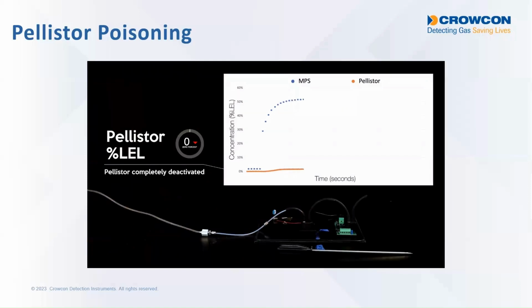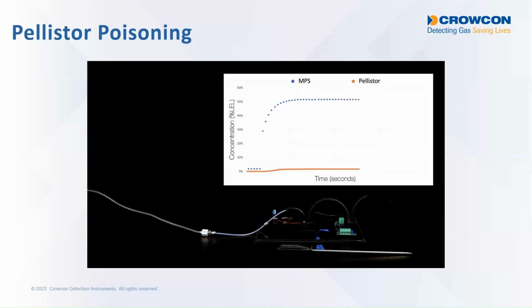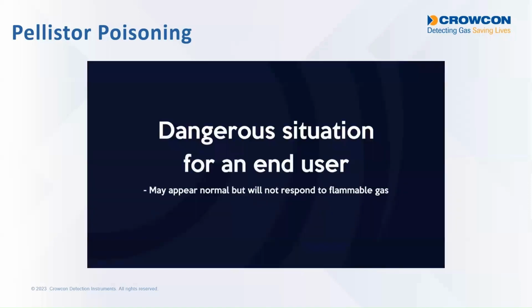So you can see on the follow-on test, now more methane is introduced to the chamber, the MPS sensor responds, the Pellistor doesn't respond at all. And that's a dangerous situation because the Pellistor remains electrically operational. The instrument thinks the Pellistor is fine. Current's still flowing through it, it just doesn't respond to gas.